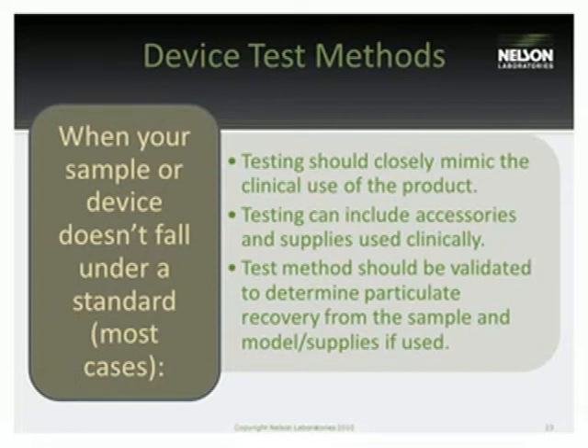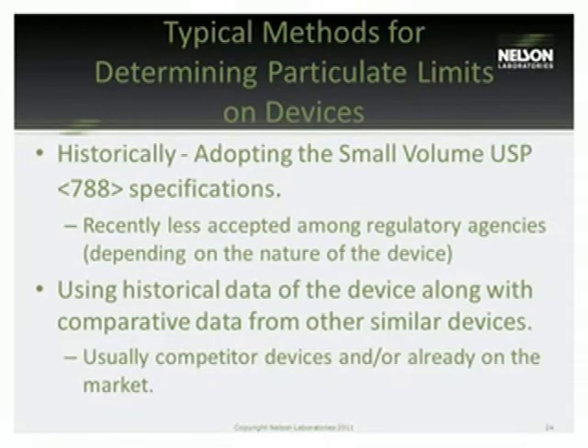In some cases, the particulate matter that's generated may be retained within the model, if a model is used during testing, or other accessory devices. Most regulators like to see a significant recovery of particulates, usually over 90% of what's subjected into a model or accessories during testing.